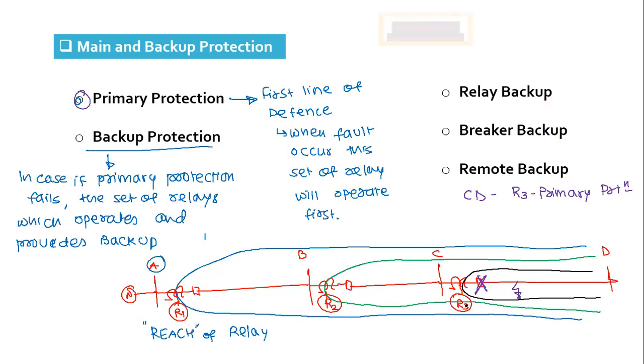Suppose relay R3 has operated correctly, but it energizes the auxiliary relay, and the auxiliary relay may not have operated correctly. Then also the circuit breaker is not tripped. Suppose everything is fine, but the control circuit is supplied by the battery, and the battery is not maintaining the terminal voltage, and at the time of tripping cannot supply the trip current. Fine, the battery is also okay, but the breaker contacts got jammed and could not separate. There is a problem with the spring or energizing element or anything, and for any reason the breaker does not open. So understand, when the breaker does not operate, it is a failure of the protective scheme, it is not a failure of the relay. Clear? Any reason could be possible.